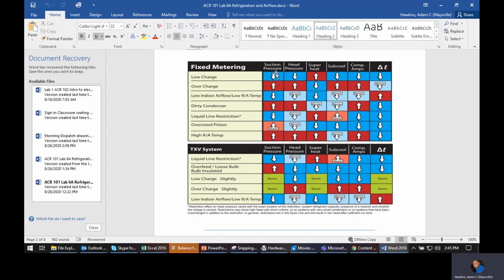Now there's other factors. Obviously, if you go on over, delta is different on those, so that may be a deciding factor. But for the people that only use their gauges, I've seen people do this. I've done this myself. You start putting refrigerant in one because your pressures are low. It doesn't get any better, and now all of a sudden you've got other issues going on. So you don't want to start overcharging a system thinking that it's undercharged, but it's really easy to do because if you only use your gauge pressures, it's going to look like it's low.